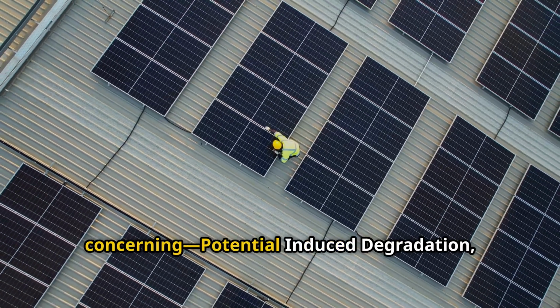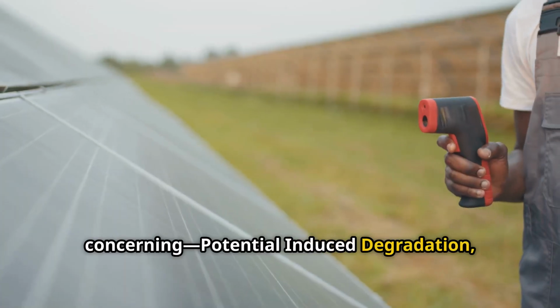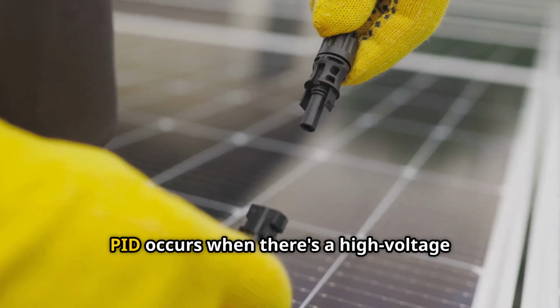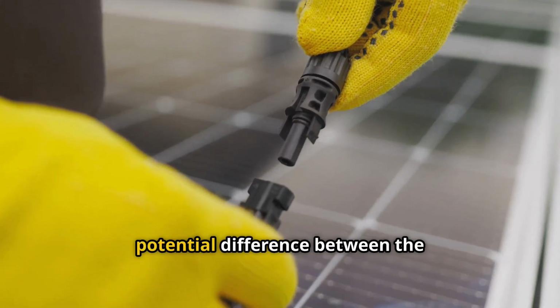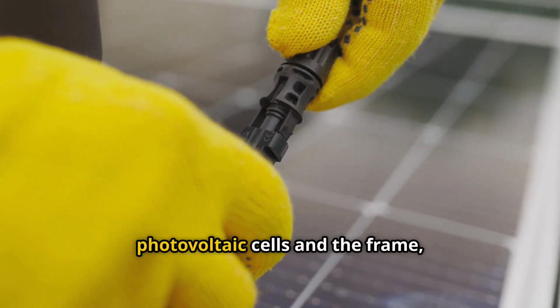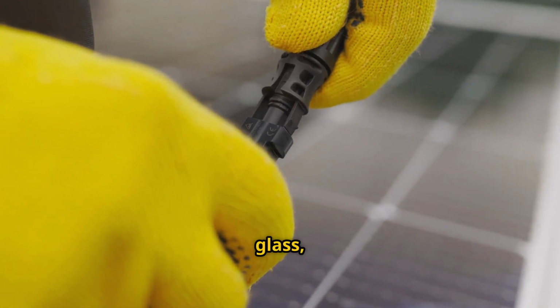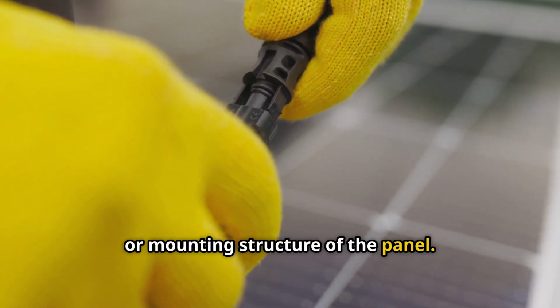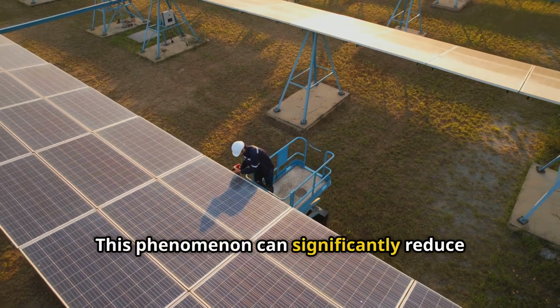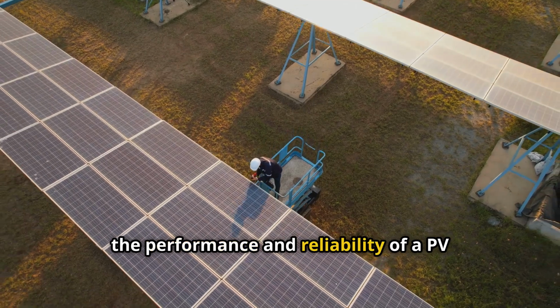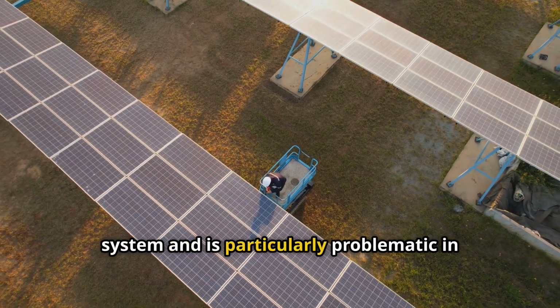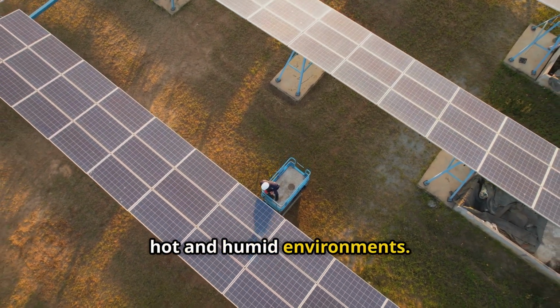Here's where it gets really concerning: potential induced degradation, or PID. PID occurs when there's a high voltage potential difference between the photovoltaic cells and the frame, glass, or mounting structure of the panel. This phenomenon can significantly reduce the performance and reliability of a PV system, and is particularly problematic in hot and humid environments.